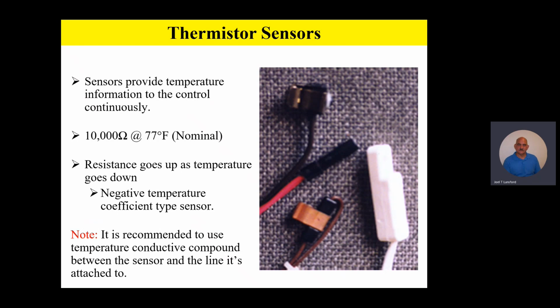So if the technician was to remove a sensor from the control board and subject that sensor to 77 degrees, let's say he had a glass of water that he knew was 77 degrees, and he put that sensor in, I always recommend taking some saran wrap so you don't soak the sensor in water, even though it probably wouldn't hurt it. It's not a good idea to just soak it in water.